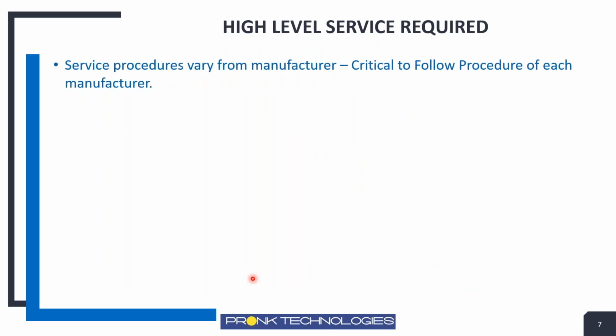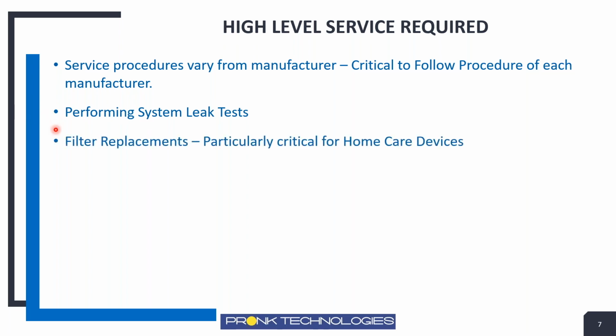as you know. So we have to do a high level of service on this. I'm sure I don't have to repeat it to you. Following the manufacturer's procedure is important. These devices are very uniquely designed depending on their application. So it's not as if one PM procedure can apply to them all. So we have to make sure that we're always trying to follow the manufacturer's procedure as it's outlined. These ventilators have a wide range of tests that need to be performed, including system leak tests, which are critical. Filter replacements are very critical from the clinical use and even during the PMs, particularly in home care devices if you have to service those devices.